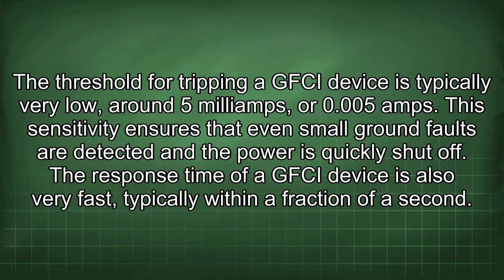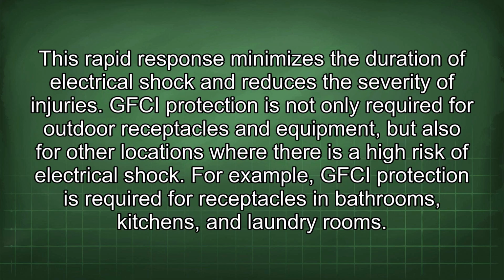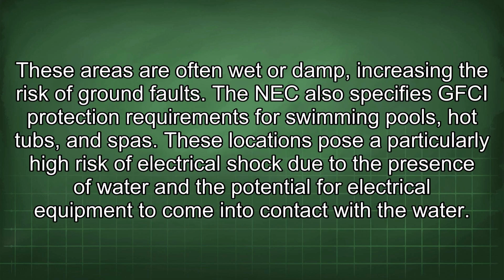This sensitivity ensures that even small ground faults are detected and the power is quickly shut off. The response time of a GFCI device is also very fast, typically within a fraction of a second. This rapid response minimizes the duration of electrical shock and reduces the severity of injuries. GFCI protection is not only required for outdoor receptacles and equipment, but also for other locations where there is a high risk of electrical shock. For example, GFCI protection is required for receptacles in bathrooms, kitchens, and laundry rooms. These areas are often wet or damp, increasing the risk of ground faults.